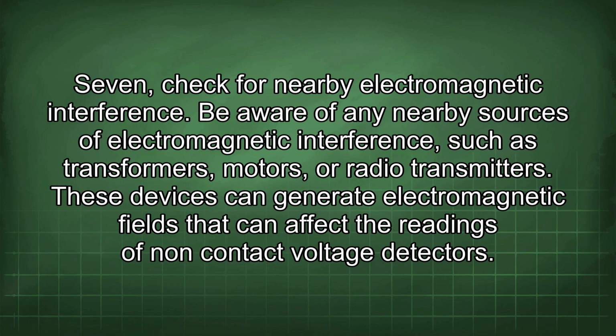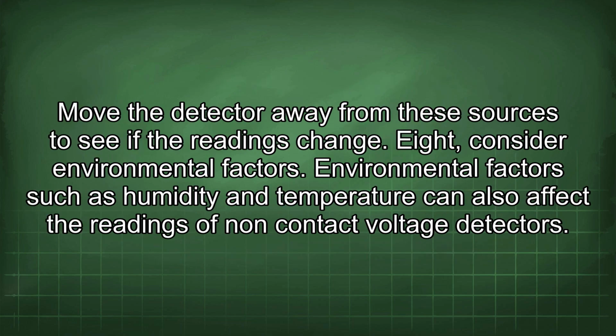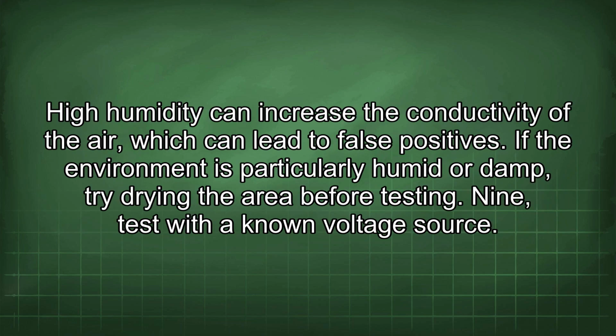7. Check for nearby electromagnetic interference. Be aware of any nearby sources of electromagnetic interference, such as transformers, motors, or radio transmitters. These devices can generate electromagnetic fields that can affect the readings of non-contact voltage detectors. Move the detector away from these sources to see if the readings change. 8. Consider environmental factors. Environmental factors such as humidity and temperature can also affect the readings of non-contact voltage detectors. High humidity can increase the conductivity of the air, which can lead to false positives. If the environment is particularly humid or damp, try drying the area before testing.